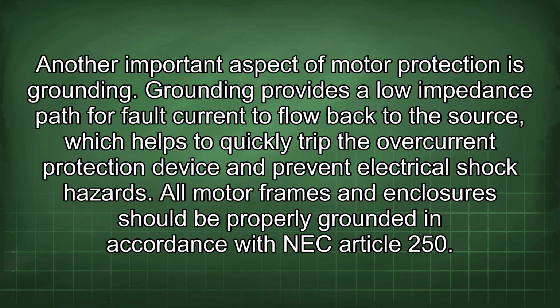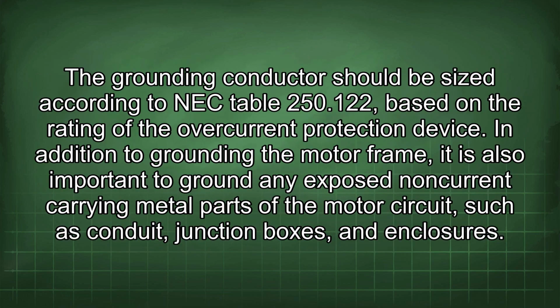Another important aspect of motor protection is grounding. Grounding provides a low impedance path for fault current to flow back to the source, which helps to quickly trip the overcurrent protection device and prevent electrical shock hazards. All motor frames and enclosures should be properly grounded in accordance with NEC Article 250. The grounding conductor should be sized according to NEC Table 250.122, based on the rating of the overcurrent protection device.